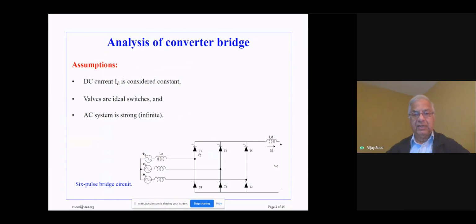So these 6 valves are indicated as T1, T3, T5, T4, T6, and T2. This is the attached AC system. The AC system is assumed to be strong, i.e. it's an infinite system. Therefore, the AC voltage does not vary. The 3 phases are indicated, EA, EB, EC. The commutation impedance is indicated as LC. This could be part of the transformer, which is connected to the converter bridge. And this could be the inductance of the transformer, or it could be a separate inductance which could be added in.